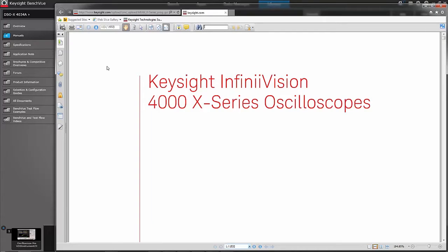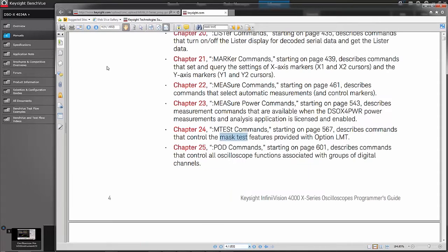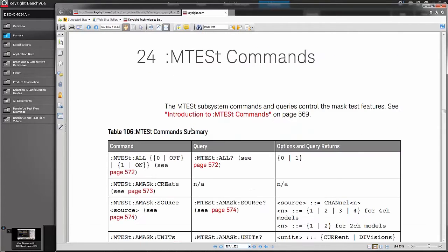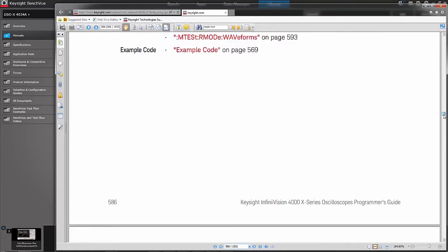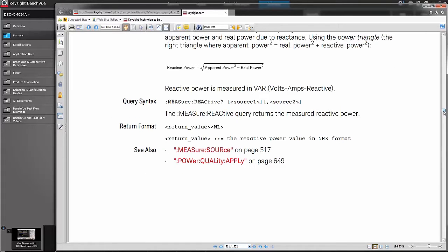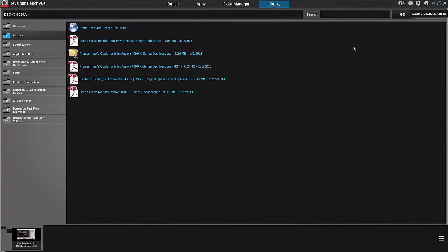Today we're going to be showing you how to do a mask test using the Oscilloscope, so I'm going to search for mask test. And it tells me that it's in chapter 24. I can go to the introduction, and here I now see some sample code that tells me how to use that feature in the application.